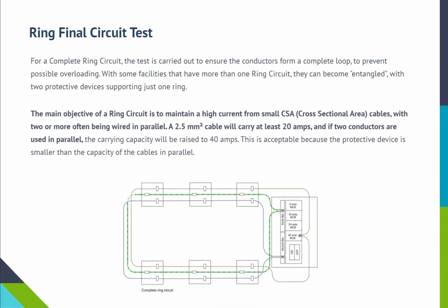For a complete ring circuit, the test is carried out to ensure the conductors form a complete loop to prevent possible overloading. With some facilities that have more than one ring circuit, they can become entangled with two protective devices supporting just one ring. The main objective of a ring circuit is to maintain a high current from small CSA, cross-sectional area, cables, with two or more often being wired in parallel.